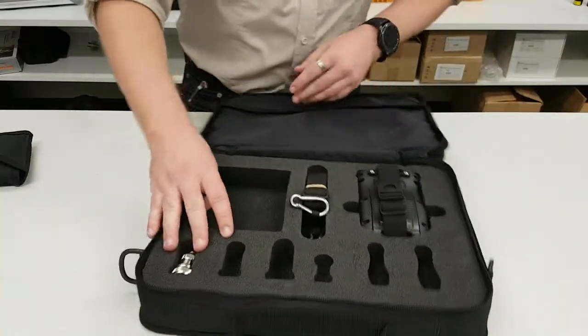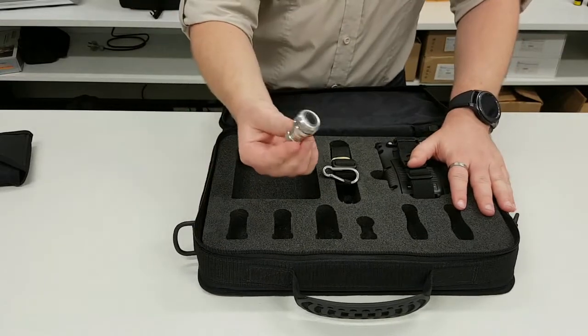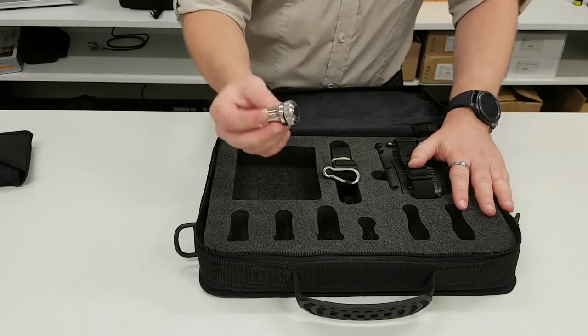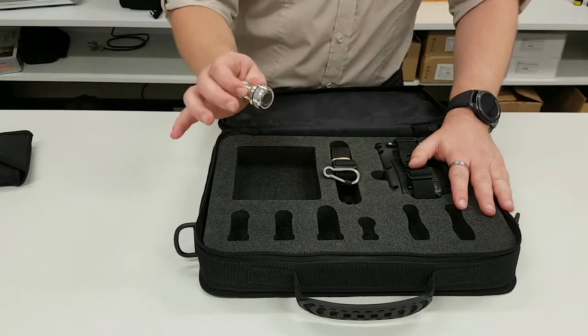On the front there are cutouts for all the probe options. By standard we've just got the S2C probe — this is a 2.25 MHz 13mm probe, standard for all the Cygnus gauges. But there are a couple of other options available that fit nice and snugly in there.